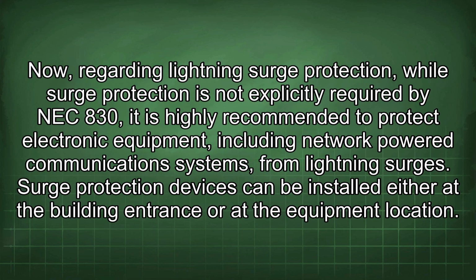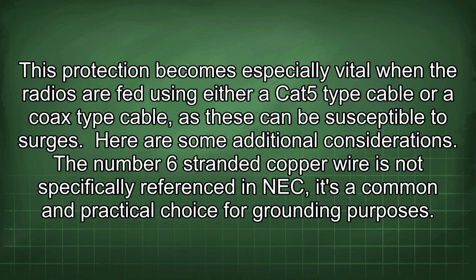Now, regarding lightning surge protection, while surge protection is not explicitly required by NEC 830, it is highly recommended to protect electronic equipment, including network-powered communication systems, from lightning surges. Surge protection devices can be installed either at the building entrance or at the equipment location. This protection becomes especially vital when the radios are fed using either a Cat5-type cable or a coax-type cable, as these can be susceptible to surges.